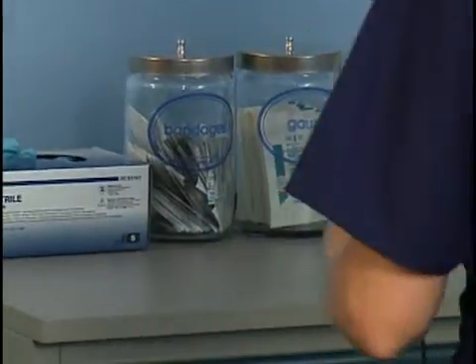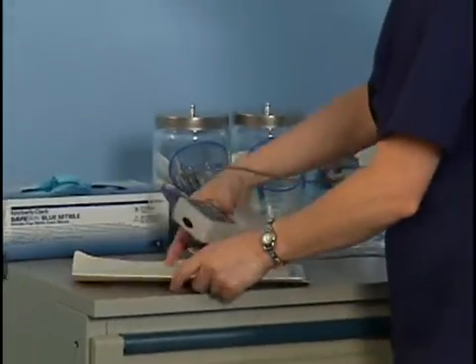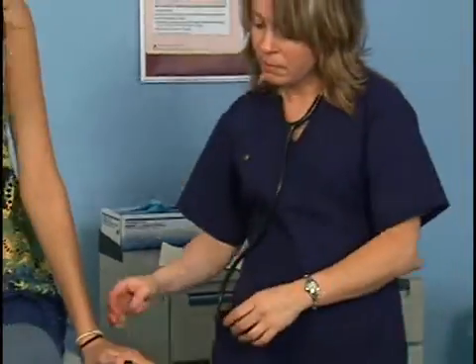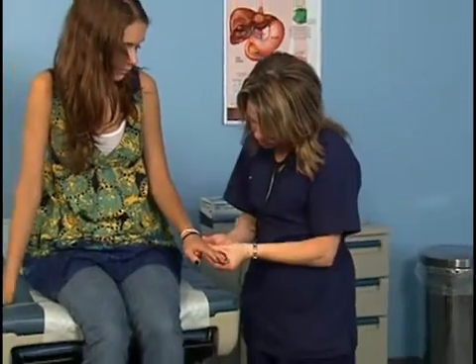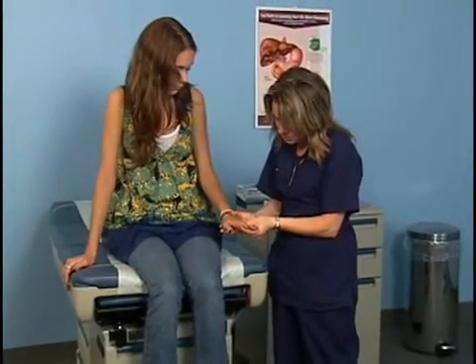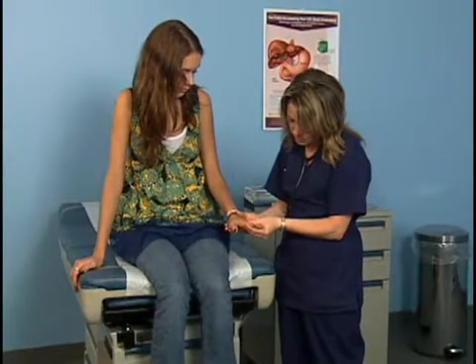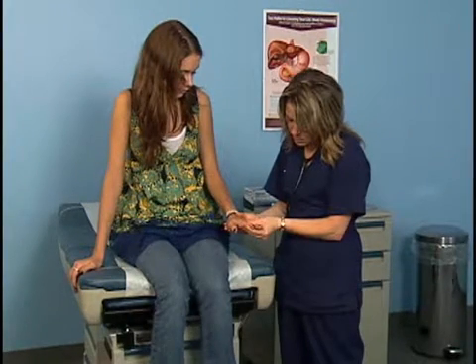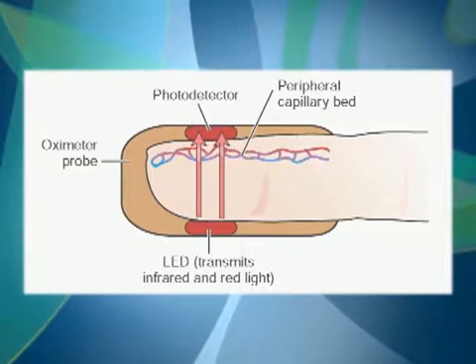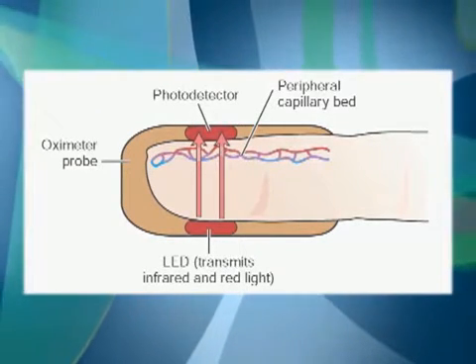The patient should be seated comfortably with the lower arm firmly supported to prevent the patient from moving her hand, which could cause an inaccurate reading. Position the hand with the palm facing down. Select an appropriate finger to apply the probe. The highly vascular tips of the patient's index, middle, and ring fingers are good sites to use.